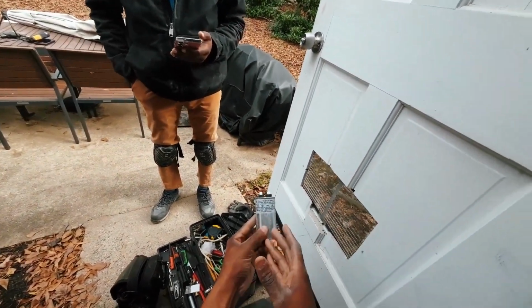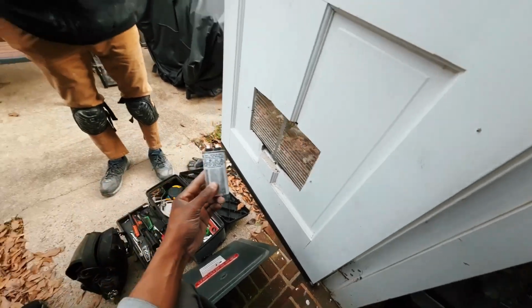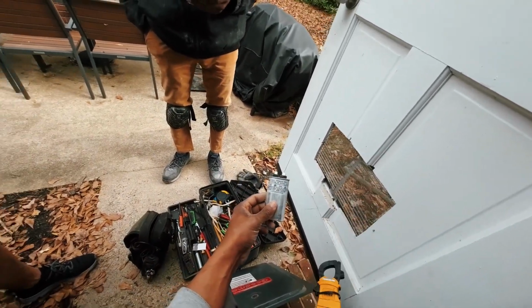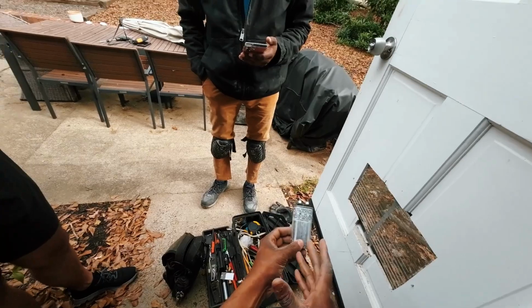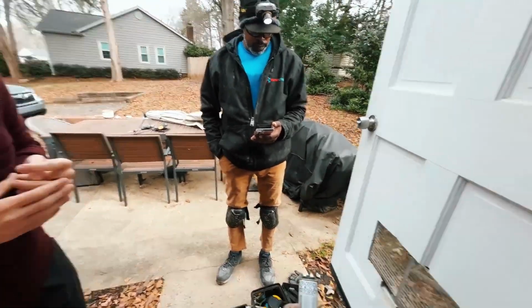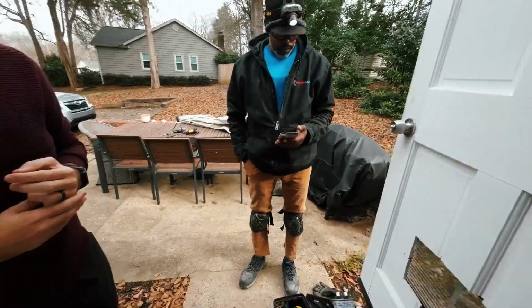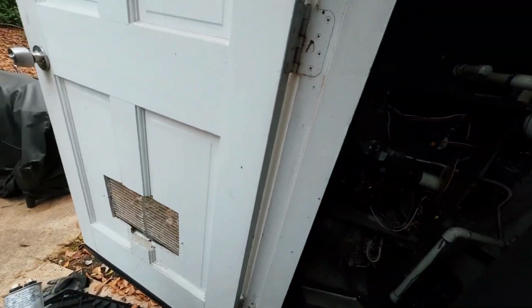It's below 5% of its rating at 10.8, and like I said, you can keep it in there and keep it running. But if it fails within the circuit, it could potentially burn the internal windings in the motor.